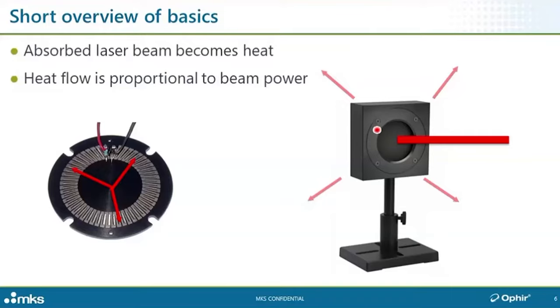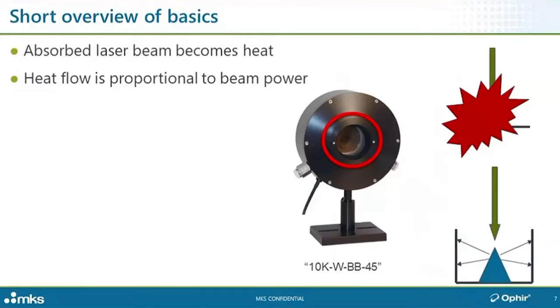Here are some smaller disks for obviously lower power sensors — you can still see the thermopile. Here's an even smaller disk. I mentioned the other half of the measurement instrument — the meter. Here you see an example of a meter with a cable going out to the sensor. I'm keeping the information as generic as possible so it'll be helpful to as many of you as possible, including those using equipment that's not Ophir. The concepts are the same.